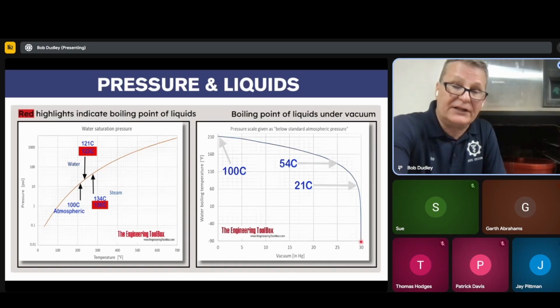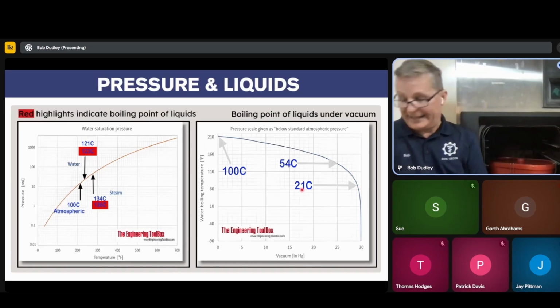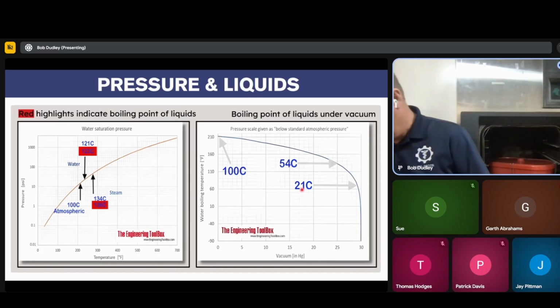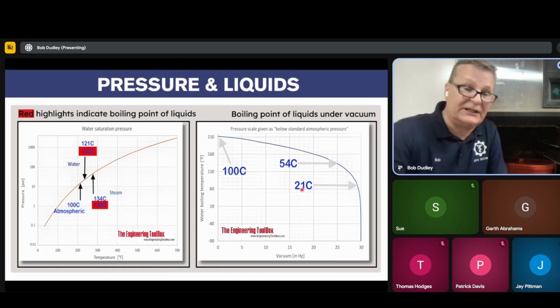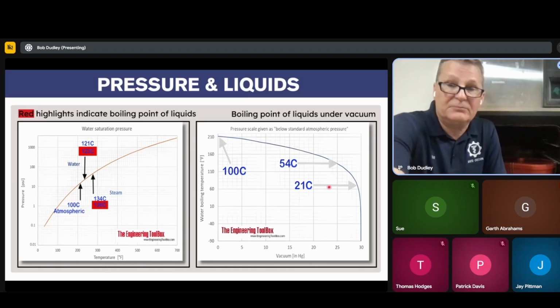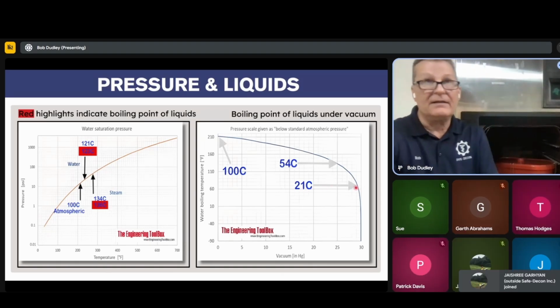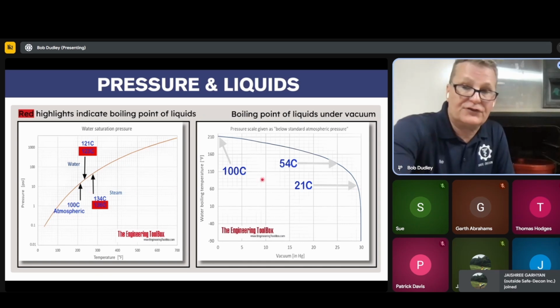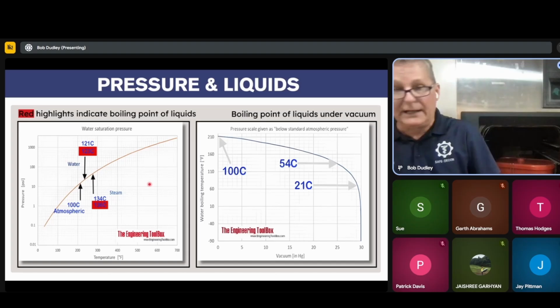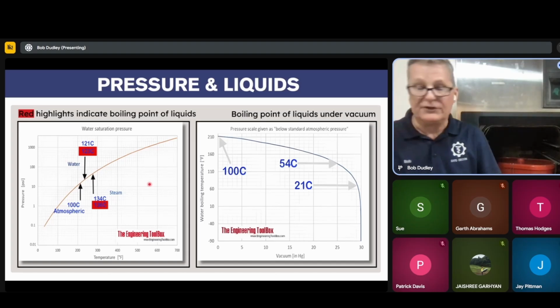Now at 30 inches, that's almost the vacuum of space right there. So you get your autoclave, and your autoclave is really good. And now you're running to 29 inches. Your boiling point is 21 C, or essentially that equates to 69 degrees. That's a beautiful spring day right there. Beautiful spring fall day, 69 degrees. And these two charts play a critical role in what happens during your cycles.